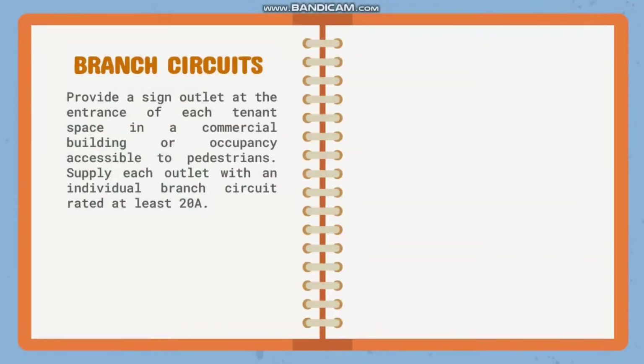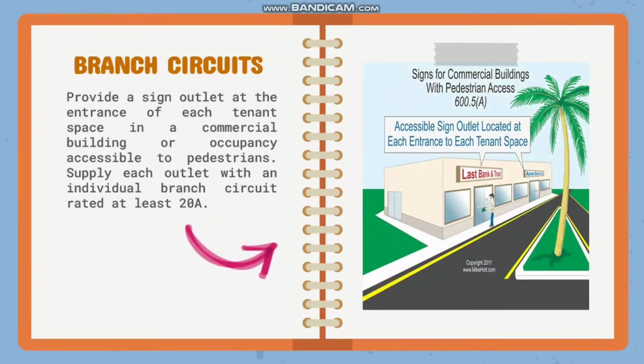So, in section 600.5(A) of PEC, requires a sign outlet for the entrance of each tenant location that is accessible to pedestrian. So, katulad ng nasa figure, so, kada tenant space is merong sign outlet na located sa entrance. Also, take note that branch circuits that supply signs are continuous loads. Ibig sabihin, nag-ooperate siya continuously within 3 hours or more. So, dapat mag-a-apply tayo ng 125% rule kapag magagawa tayo ng load calculations.